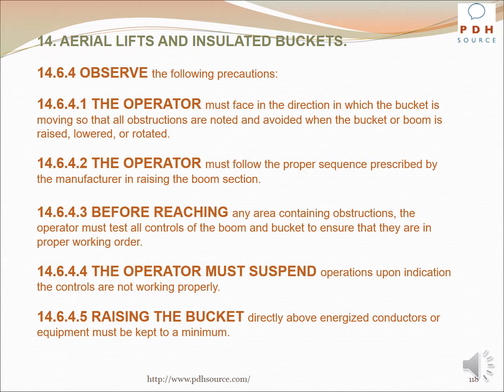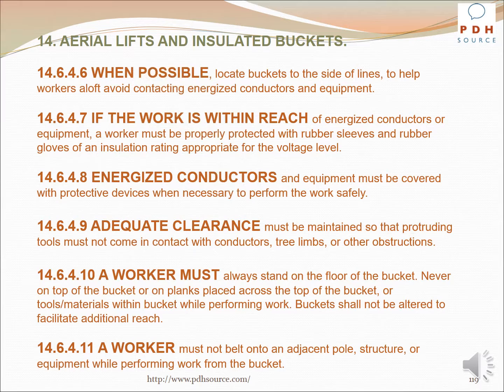Raising the bucket directly above energized conductors or equipment must be kept to a minimum. When possible, locate buckets to the side of lines to help workers avoid contacting energized conductors and equipment. If the work is within reach of energized conductors or equipment, a worker must be properly protected with rubber sleeves and rubber gloves of an insulation rating appropriate for the voltage level. Energized conductors and equipment must be covered with protective devices when necessary to perform the work safely.